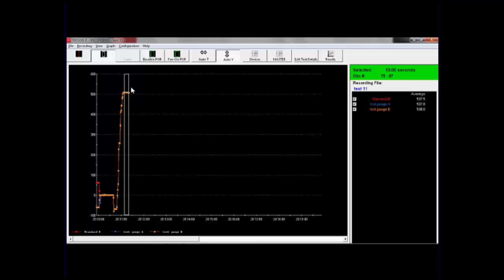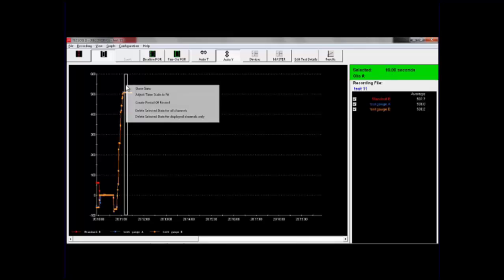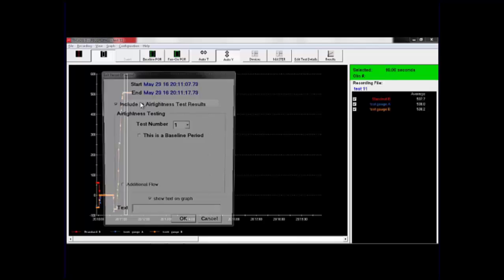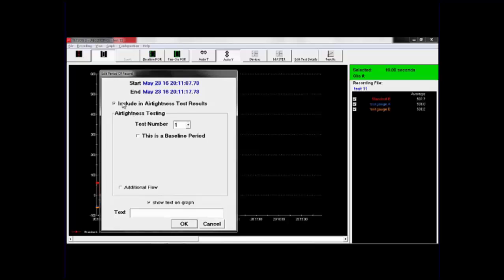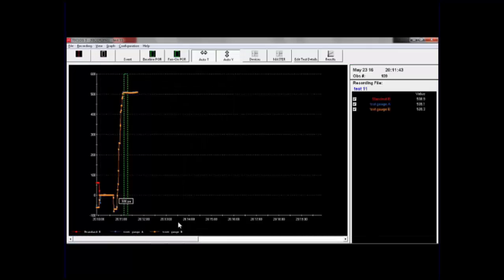And I'm just going to make a short period of record, a 10-second period of record here, and then I'm going to click in that box, and I'm going to create a period of record. And I don't want to include it in an air tightness test. We're not doing an air tightness test. And that one's 500 pascals. I'll give it a label. And then I'm going to push in the syringe to get it down to 50. So you can watch our numbers go, or you can watch the graph go. And we want to be down to 50 pascals.